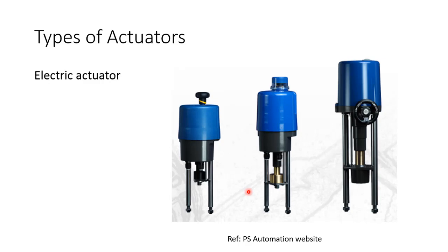It means the power required to operate is very, very little. On the other hand, the pneumatic actuator doesn't require such an enclosure, since air is used and only a weatherproof actuator can suffice. So there is air, there are mechanical components, and you can achieve the open and the closed condition, and there is no possibility of any spark. That is why you really don't require an intrinsically safe or an explosion proof actuator. Another thing is that electrical actuators are used when a compressor is not available and you require only to operate a few valves, or when the stroke of the valve is very, very high.